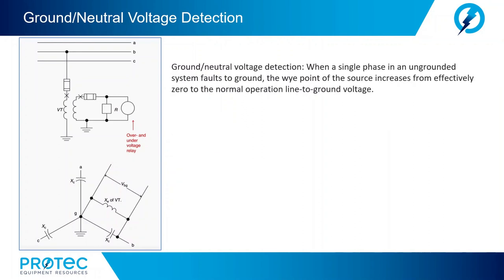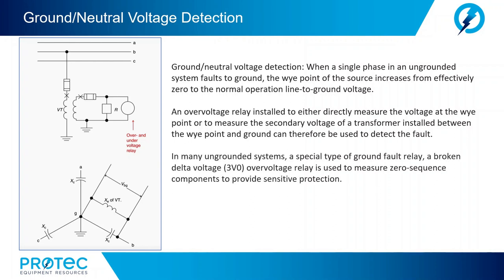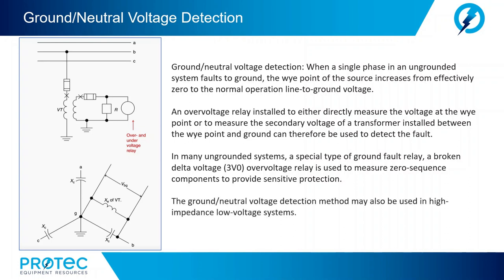When a single phase in an ungrounded system faults to ground, the Y point of the source increases from effectively zero to the normal operating line-to-ground voltage. An overvoltage relay installed to either directly measure the voltage at the Y point or to measure the secondary voltage of a transformer installed between the Y point and ground can be used to detect the fault. In many ungrounded systems, a special type of ground fault relay — a broken delta voltage overvoltage relay — is used to measure zero sequence components to provide sensitive protection. The ground neutral voltage detection method may also be used in high impedance, low voltage systems.